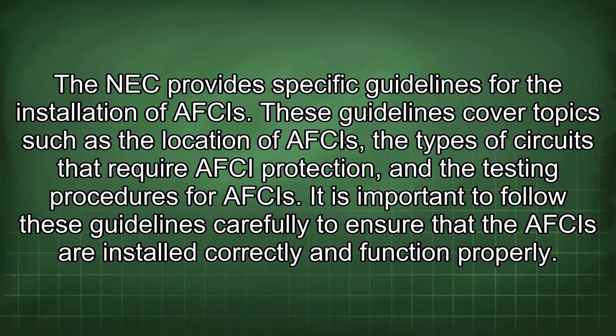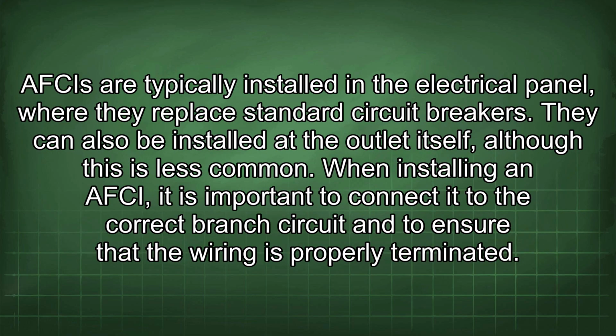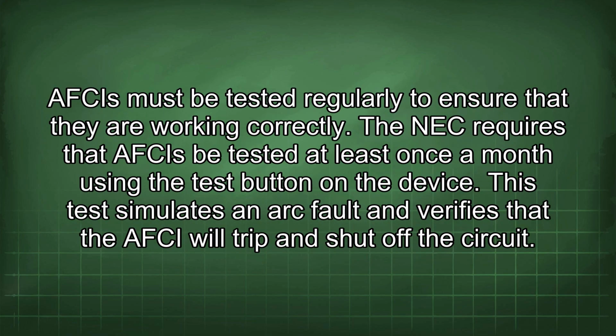The NEC provides specific guidelines for the installation of AFCIs. These guidelines cover topics such as the location of AFCIs, the types of circuits that require AFCI protection, and the testing procedures for AFCIs. It is important to follow these guidelines carefully to ensure that the AFCIs are installed correctly and function properly. AFCIs are typically installed in the electrical panel, where they replace standard circuit breakers. They can also be installed at the outlet itself, although this is less common. When installing an AFCI, it is important to connect it to the correct branch circuit and to ensure that the wiring is properly terminated.